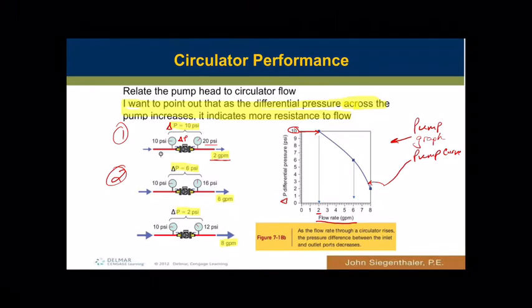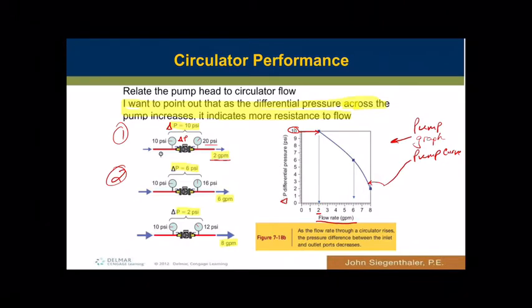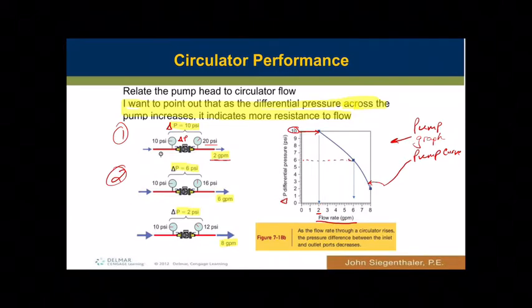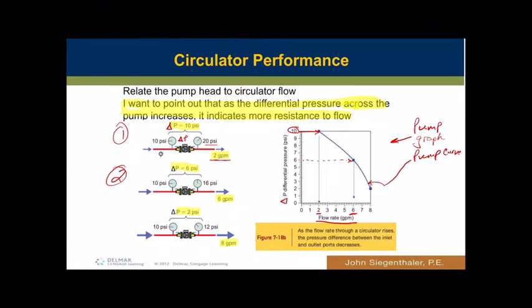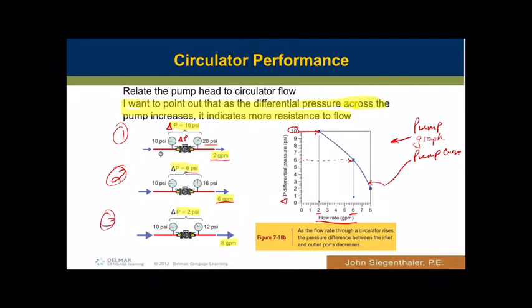The second point has a delta P of 6 PSI: 10 PSI going in, 16 PSI coming out. That tells me the system has less resistance in the same system and would have more GPM. Looking at its pump curve, we go across until it intersects the curve and find that is six gallons a minute. Six GPM is the flow rate, and 6 PSI is the delta P.